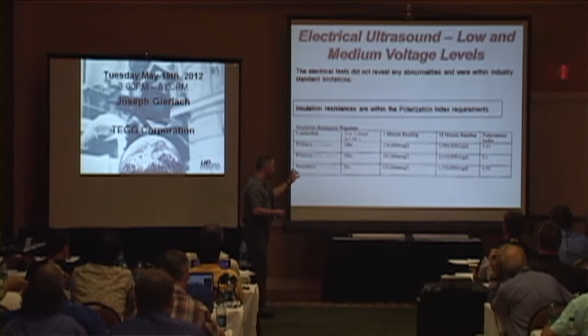And what you look for from a maintenance testing standpoint here is you apply a voltage, ideally above the rating of the insulation, for a period of time, and gauge those results against what's called a polarization index. Essentially the test voltage is applied for a 10-minute period, and the device is measuring leakage currents. When you first apply the test voltage, the resistance is very low because there's a lot of leakage current, and it eventually seals off. It's a charging current on large equipment. It takes some time to stabilize. So you'll typically have lower values of resistance that climb over this 10-minute period. To determine the polarization index, you simply take the 10-minute measurement divided by the 1-minute measurement, and the higher the better. If it's a flat line or it goes down, there's a problem.